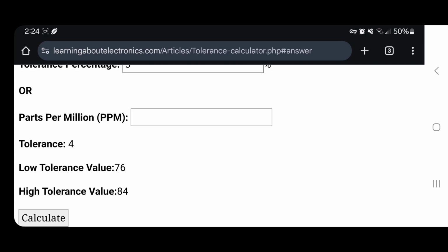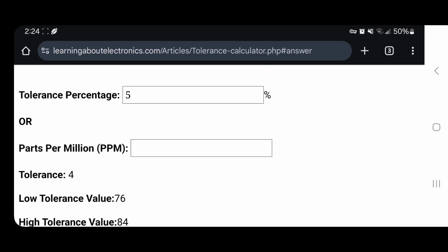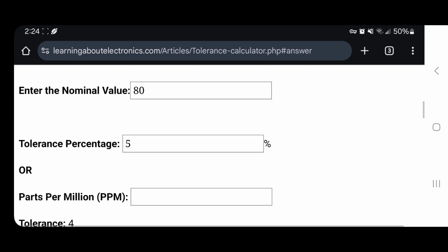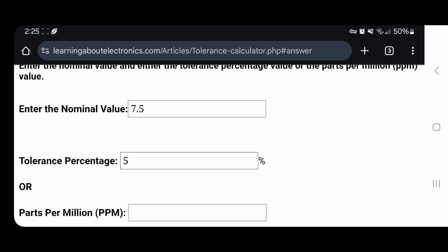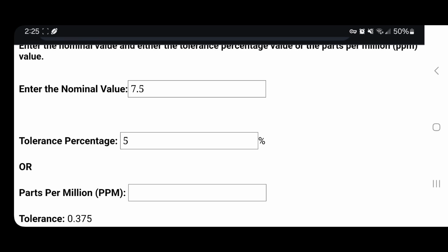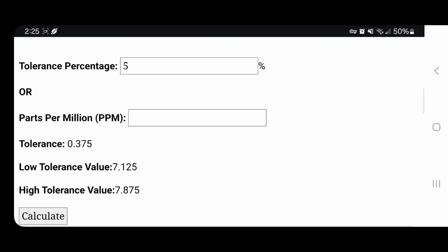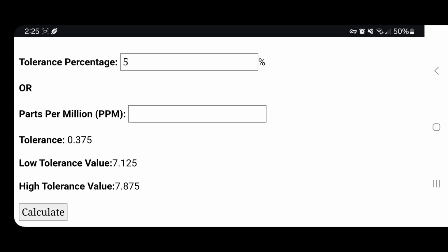I'm probably going to go ahead and replace this cap, get one on order and get it replaced. Now I need to check the percentage of the other lead, and at 7.5, I'm getting a reading of 7.33. That's well within tolerance, so we could call that one good. But like I said, the other one is right there at the lower end of our tolerance, so I will be replacing that one.